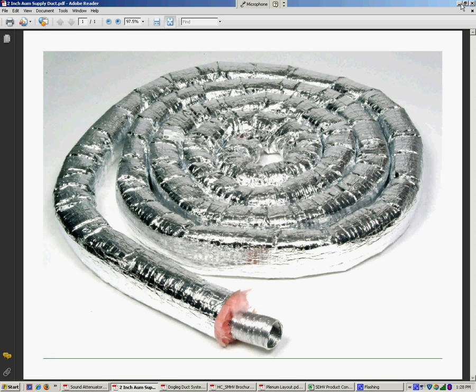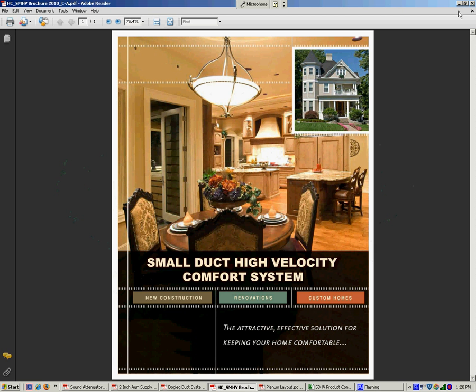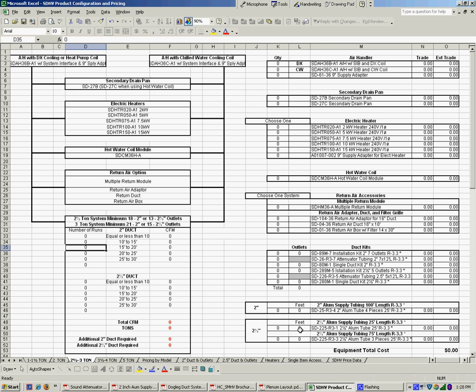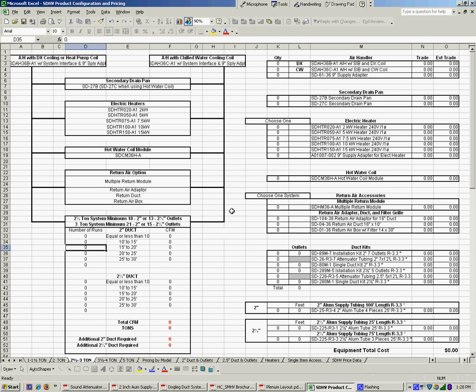So once we've determined we're going to do this system and we understand what the load is on the house. In this case, let's say we have a three-ton load. We're going to put in a three-ton system. As you can see, this thing is designed for a ton and a half up through five-ton applications. The left-hand side is basically a ladder that's going to take you through the process of picking out the materials you're going to use on the job.